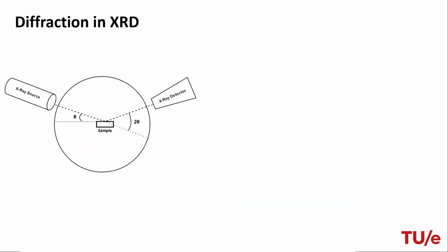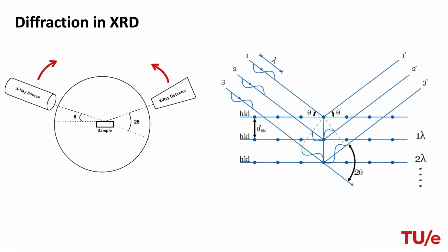X-ray diffraction is made up of three main components: the X-ray source, the sample and sample holder, and the X-ray detector. The X-ray beam is created, which is then diffracted by the sample and collected by the X-ray detector. The detector moves in sync with the X-ray source. At certain angles, the X-rays overlap in phase, producing constructive interference. One constructive interference to another occurs in increments of a whole number of wavelengths, n. By measuring the angle of the scattered rays and knowing how many extra wavelengths are traveled, we can calculate the space between atomic planes. This relationship is given by Bragg's law.